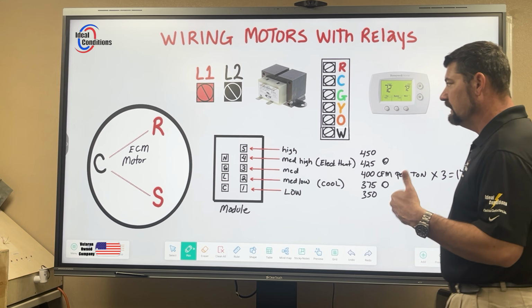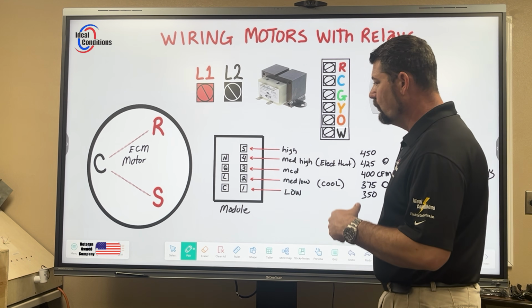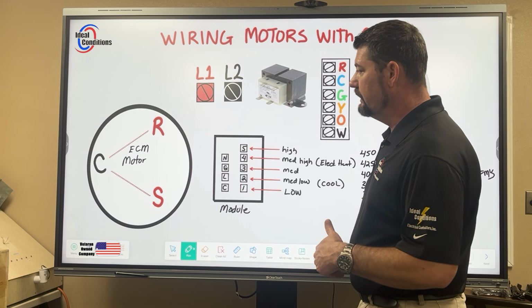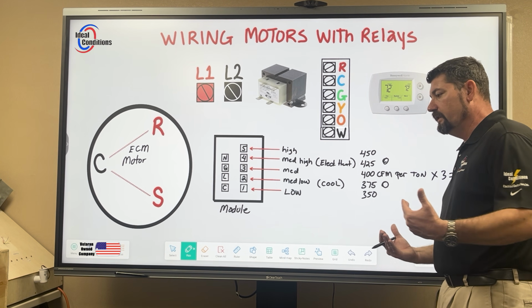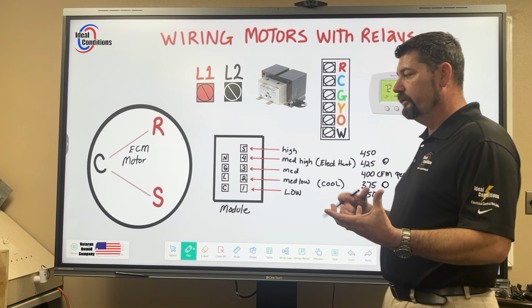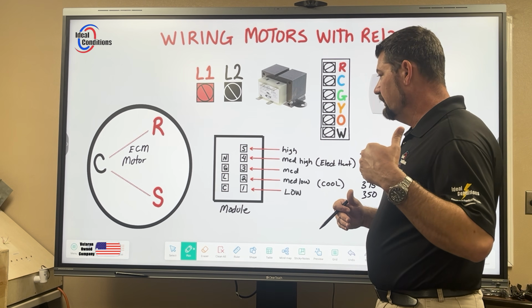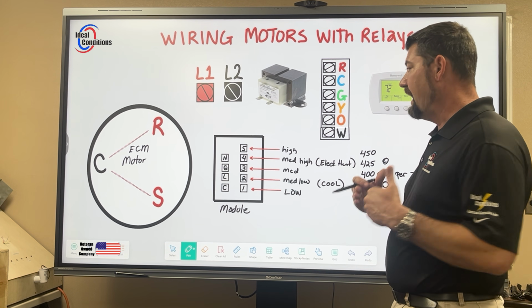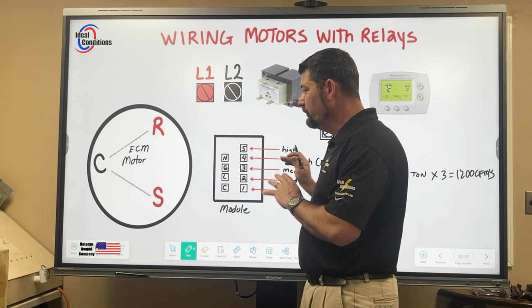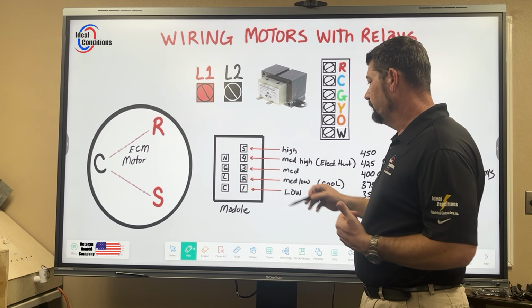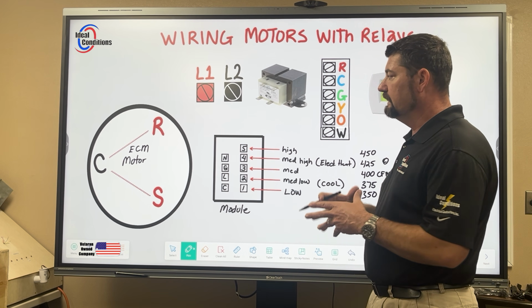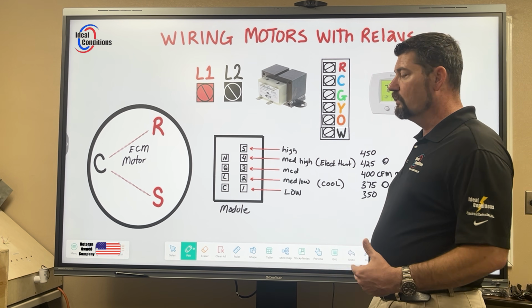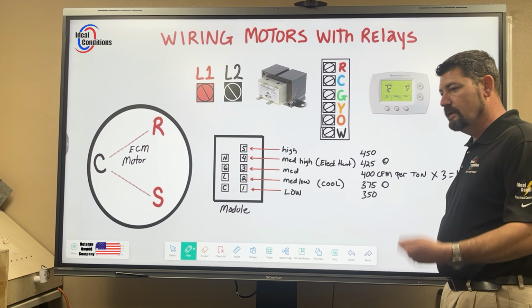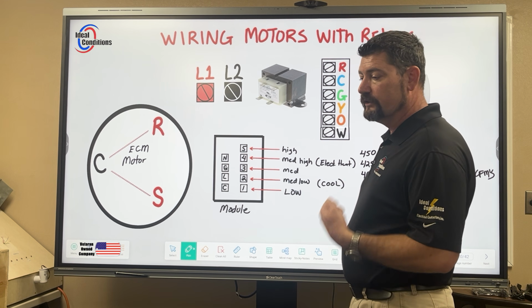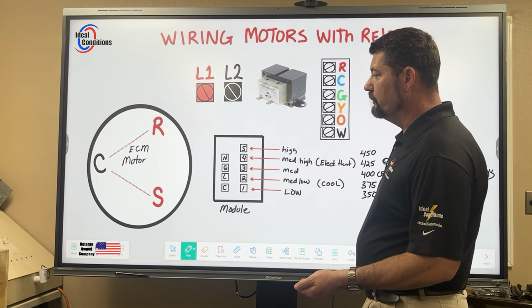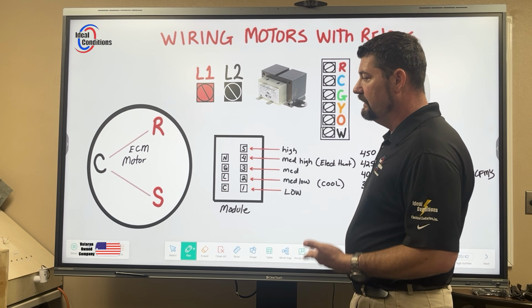And we talked about that off delay extensively with the blower control boards and certain relays like sequencers, and any relay that pretty much has a built-in 24 volt power supply to allow the relay to stay energized anywhere between 50 to 90 seconds after the G call is gone. This module does the same thing. So you're still getting that, plus we have the 2 speeds. So a lot more comfort, a lot more efficiency. ECMs are the way to go. They also run at a lower ampacity, provided that you have the proper voltage on them. If your voltage is too low, your ampacity is going to be higher. If your voltage is right where it should be, then your ampacity will be at the design specs.